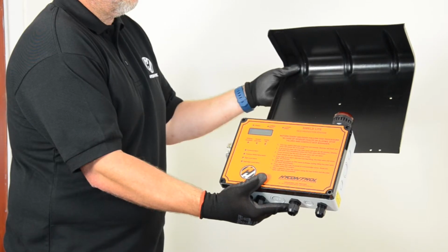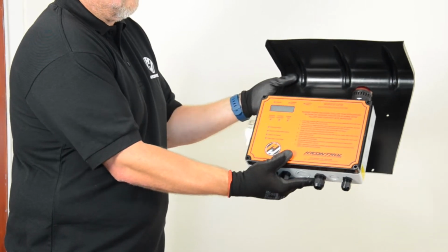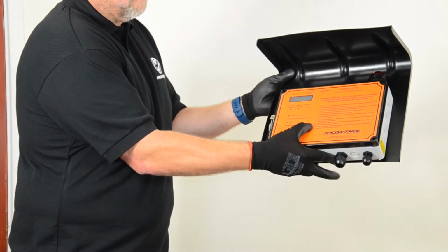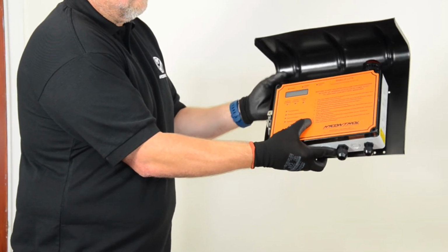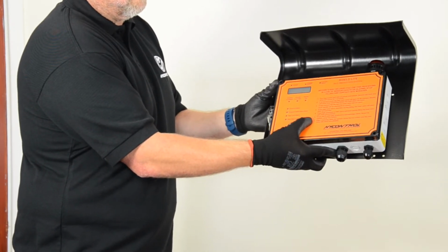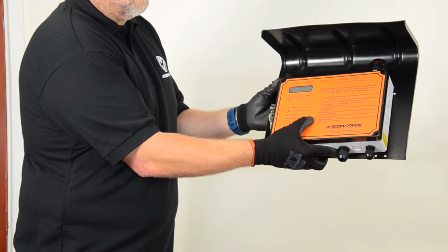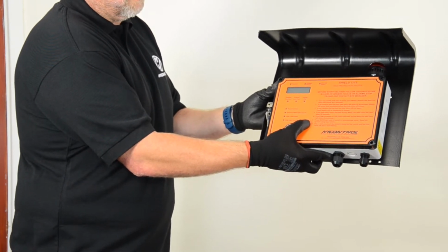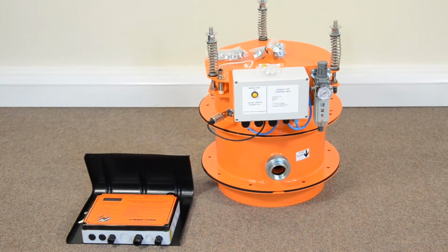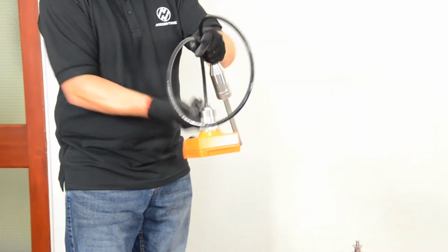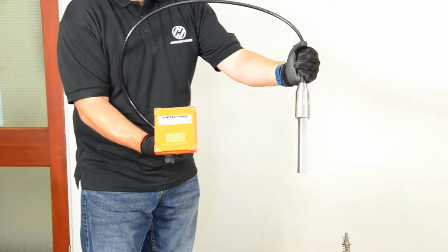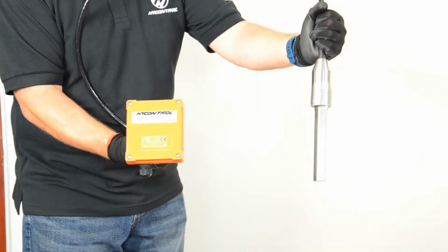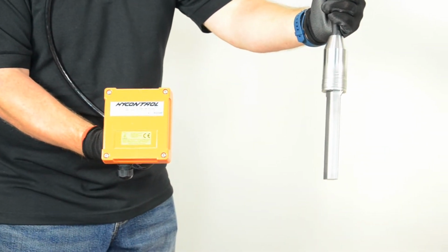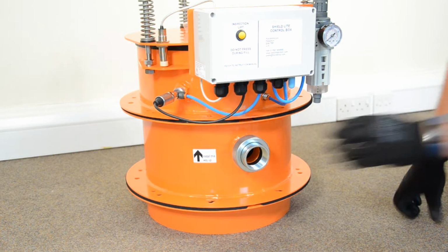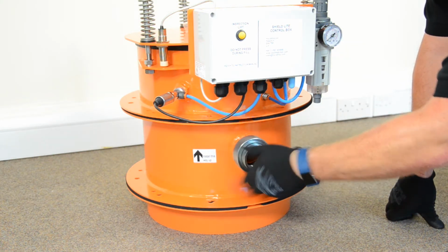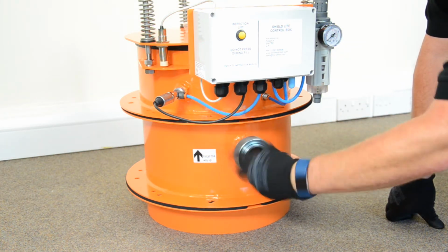Before wiring the PRV, mount the panel and its weather shield near the fill point. These use the same locating holes, so when the cover is off the panel, it can be attached through the weather shield. For this demonstration, we will place it on the floor. The final component is the high-level probe. The DP150 vibrating probe features a long cable so it can hang down inside the silo. This is mounted through the port via the upstand port's quick release coupling.